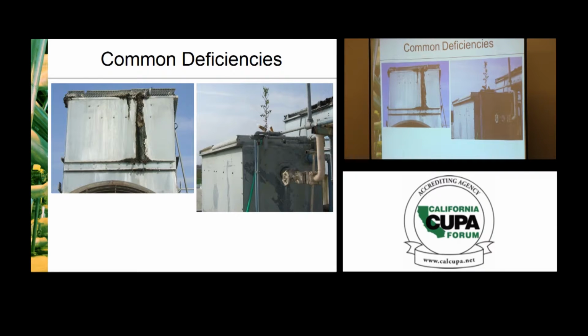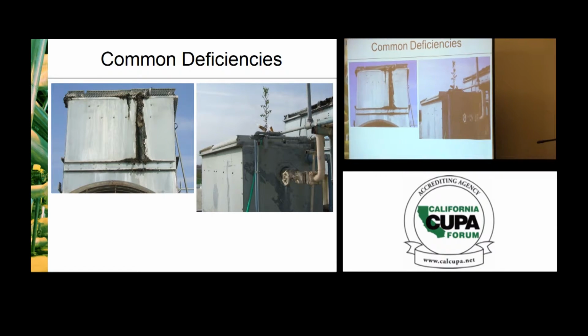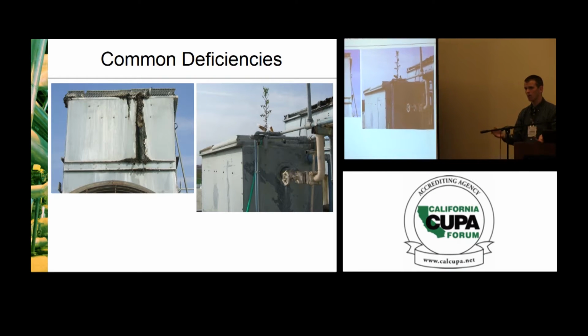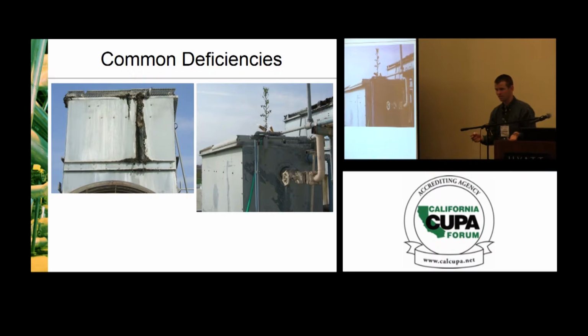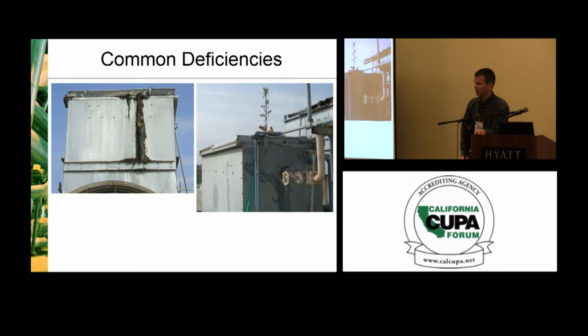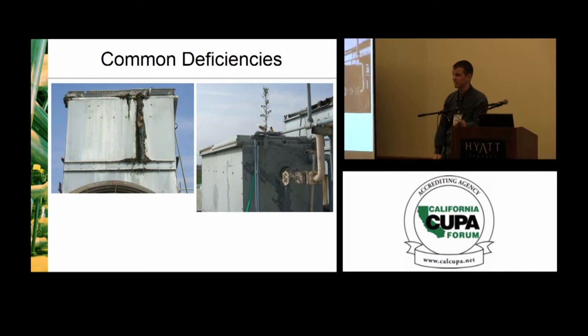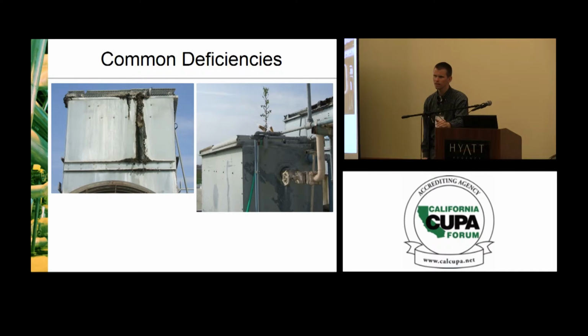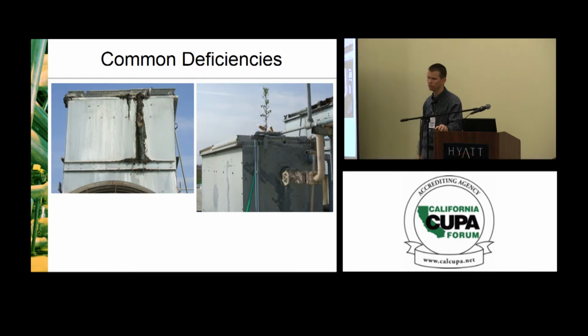So the evap condenser, when it comes to prior operating experience, when we talk about cleaning an evap condenser, prior operating experience is huge, because I think IIAR Bulletin 110 says, don't quote me on this, but I think it says every month to clean it. Something like that. For a lot of facilities, that's pretty overkill. In my opinion, it's not necessary, but prior operating experience will clearly tell you how often it should be cleaned.